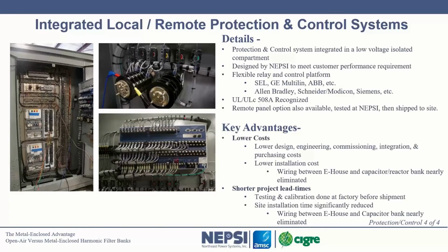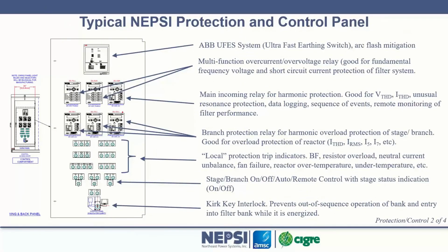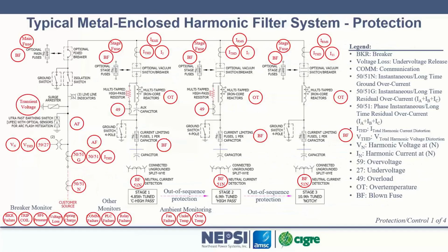When you look at it, it consists of many different types of relays. Remember that most overcurrent relays do not sense harmonic current. They are filtering out the harmonic current, and they're responding to fundamental values. And therefore, to protect harmonic filters, it's typically best to use some type of metering device. We use a Schweitzer 735, but there are other devices. But power quality meters with relay outputs can better protect a harmonic filter than an overcurrent relay can, because overcurrent relays are looking at fundamental. We like to look at all the values: RMS, THD, and various harmonic currents. So there is a complex part of the design of harmonic filters, and that is control and protection.